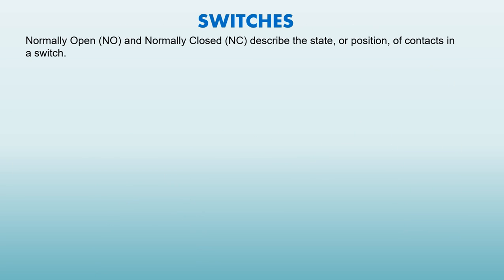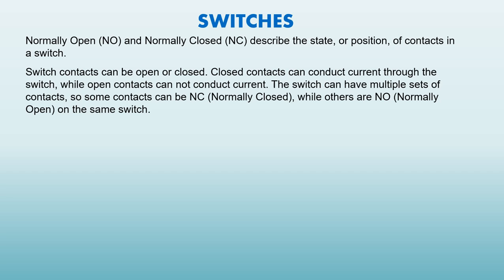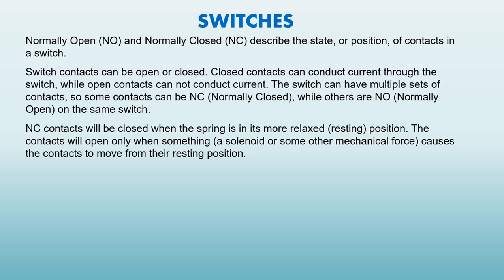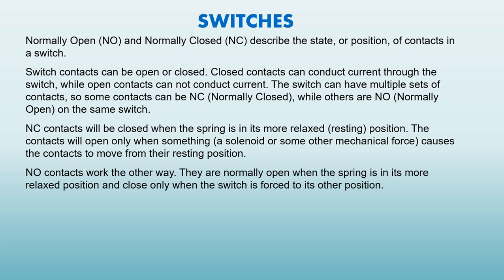Next, let's talk about switches. Normally open and normally closed describes the state or position of contacts in a switch. Switch contacts can be open or closed. Closed contacts can conduct current through the switch, while open contacts cannot conduct current. The switch can have multiple sets of contacts. So some contacts can be normally closed, while others are normally open on the same switch. Normally closed contacts will be closed when the spring is in its more relaxed or resting position. The contacts will open only when something, such as a solenoid or other mechanical force, causes the contact to move from their resting position.